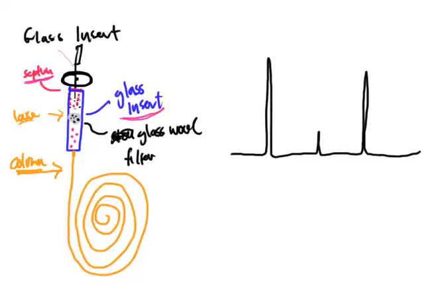But every now and then, if you've got contamination that's lodged back here and it's slowly coming into the column, you might see an extra small peak on the chromatogram. It would make you assume that there's another component in there that you traditionally haven't found, but actually it's just trash left over because the glass insert has not been changed. So always change the glass insert. It's a very good measure to take. It doesn't cost a lot of money to change those out, and it's always better to be safe than sorry.